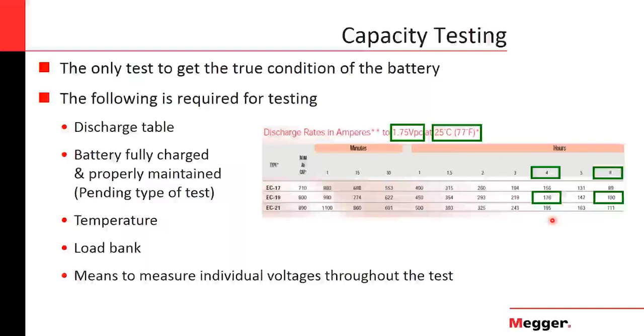And as for the instrument, what you need to run the test is a load bank, something that can do a constant draw of current or power in a very smooth and controlled way. And this load bank, this resistance bank, also needs some brains to be able to stop the test when it is required, when it reaches the minimum voltage, or if you just want to run it for the specified time, you can do that. You can stop the test with a voltage limit, time limit, or capacity limit.